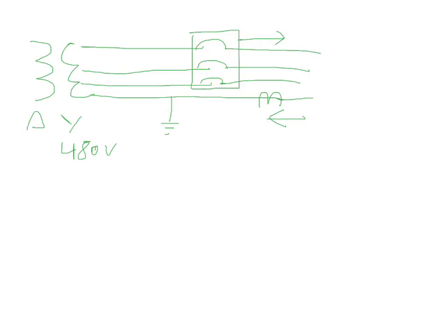One thing that we do in the field to check this ground fault test is we jumper A phase to the neutral, and then we push current through A phase, and it makes sure that it returns back and passes through the neutral CT. Once that happens, the breaker shouldn't trip.